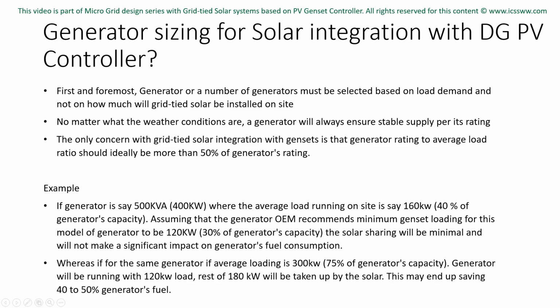The only concern with grid-tied solar integration with gensets is that the ratio of average load to generator's rating should ideally be more than 50% of generator's rating. If the generator is, say, 500 kVA, which is 400 kilowatt, and the average load running on site is, say, 160 kilowatt, which is 40% of generator's capacity, assuming that the generator's OEM recommends minimum genset loading for this model of generator to be 120 kilowatt, which is 30% of generator's capacity, the solar sharing will be minimal and will not make a significant impact on generator's fuel consumption.